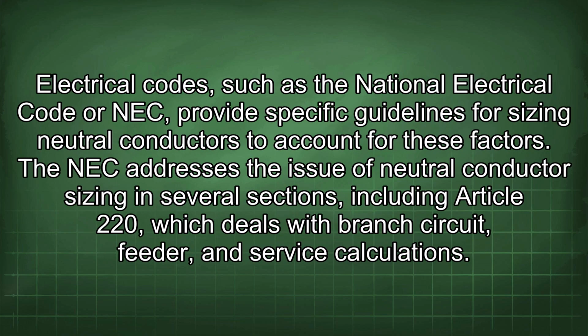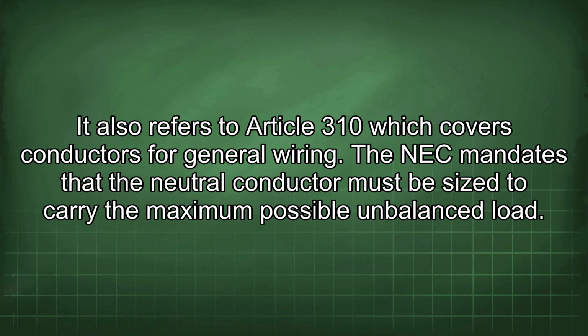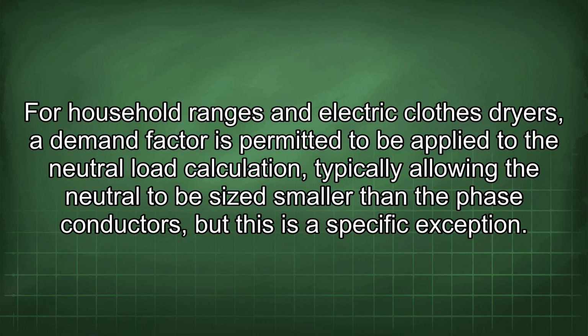Electrical codes, such as the National Electrical Code or NEC, provide specific guidelines for sizing neutral conductors to account for these factors. The NEC addresses the issue of neutral conductor sizing in several sections, including Article 220, which deals with branch circuit, feeder, and service calculations. It also refers to Article 310, which covers conductors for general wiring. The NEC mandates that the neutral conductor must be sized to carry the maximum possible unbalanced load. For household ranges and electric clothes dryers, a demand factor is permitted to be applied to the neutral load calculation, typically allowing the neutral to be sized smaller than the phase conductors, but this is a specific exception.